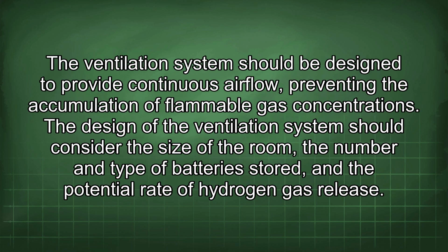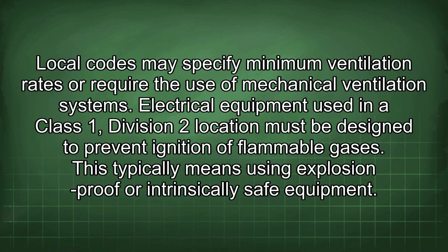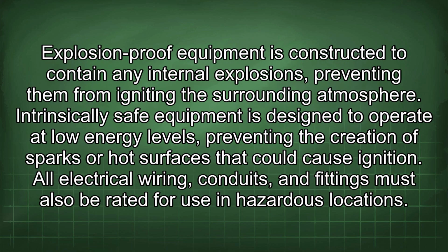The ventilation system should be designed to provide continuous airflow, preventing the accumulation of flammable gas concentrations. The design of the ventilation system should consider the size of the room, the number and type of batteries stored, and the potential rate of hydrogen gas release. Local codes may specify minimum ventilation rates or require the use of mechanical ventilation systems. Electrical equipment used in a Class 1, Division 2 location must be designed to prevent ignition of flammable gases. This typically means using explosion-proof or intrinsically safe equipment. Explosion-proof equipment is constructed to contain any internal explosions, preventing them from igniting the surrounding atmosphere. Intrinsically safe equipment is designed to operate at low energy levels, preventing the creation of sparks or hot surfaces that could cause ignition.